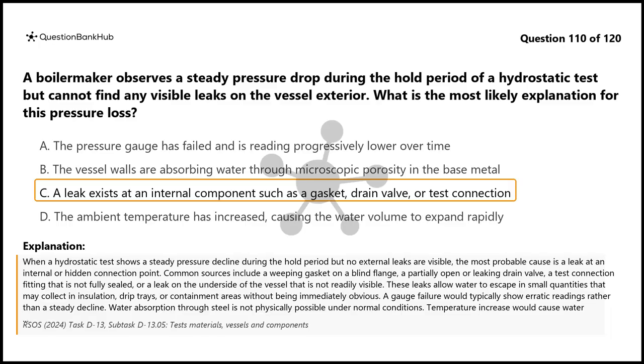These leaks allow water to escape in small quantities that may collect in insulation, drip trays, or containment areas without being immediately obvious. A gauge failure would typically show erratic readings rather than a steady decline. Water absorption through steel is not physically possible under normal conditions. Temperature increase would cause water expansion and a slight pressure rise, not a decline. Systematic inspection of all connections, valves, and the vessel underside is required to locate the leak source.